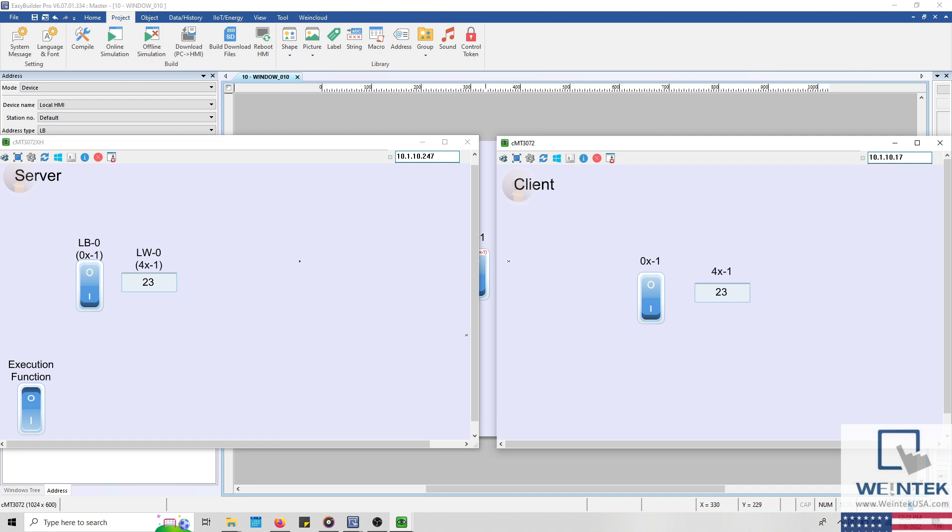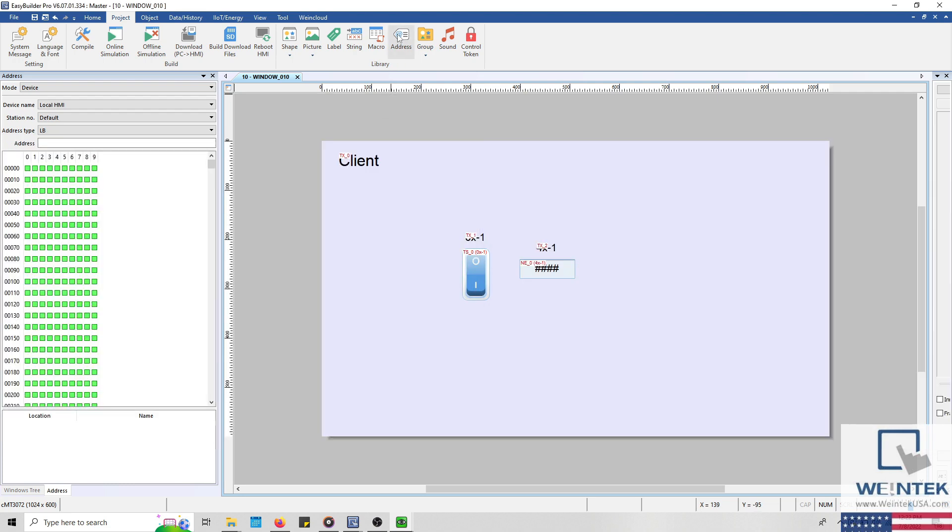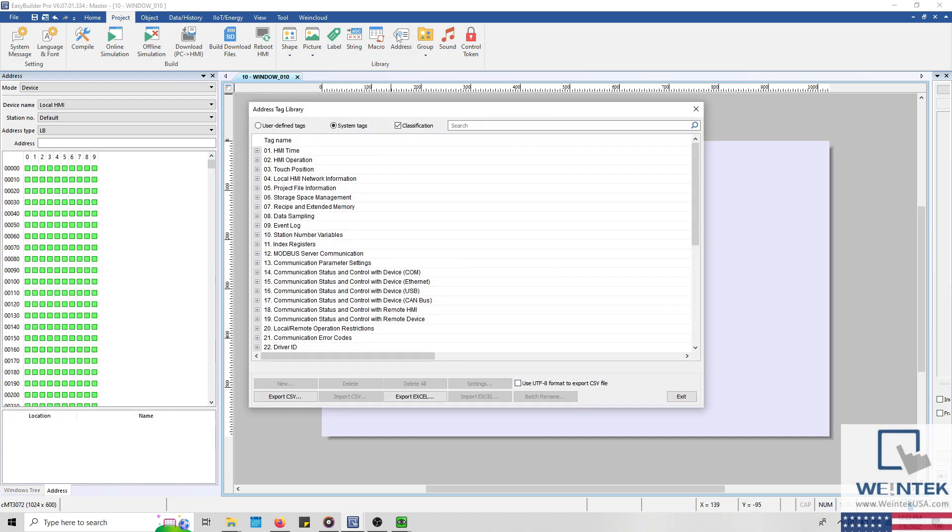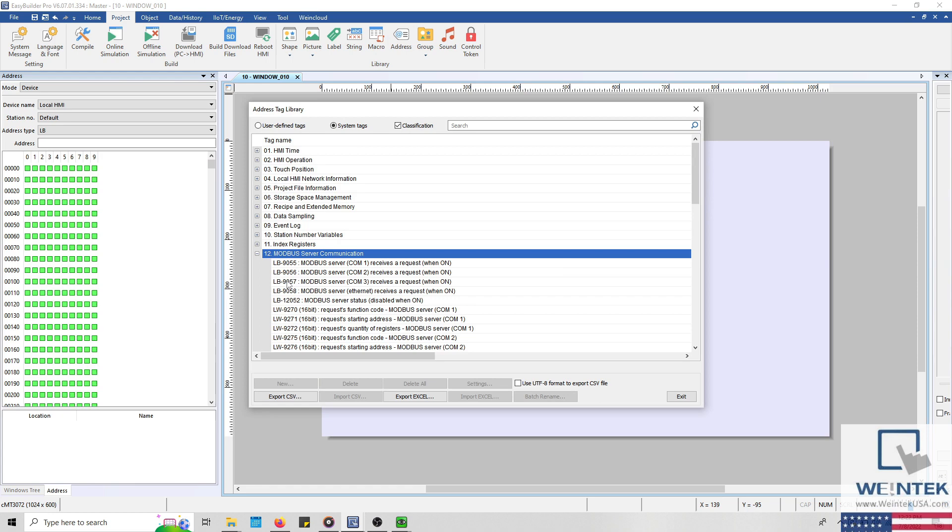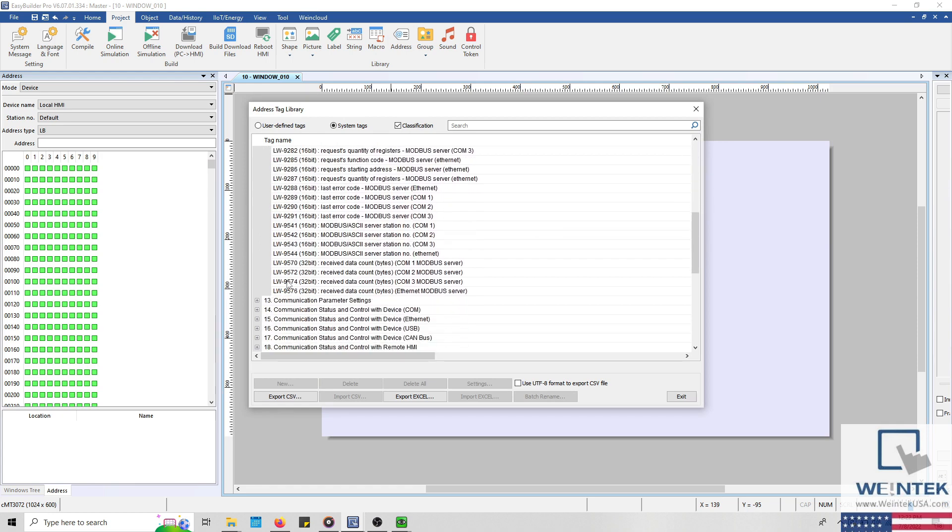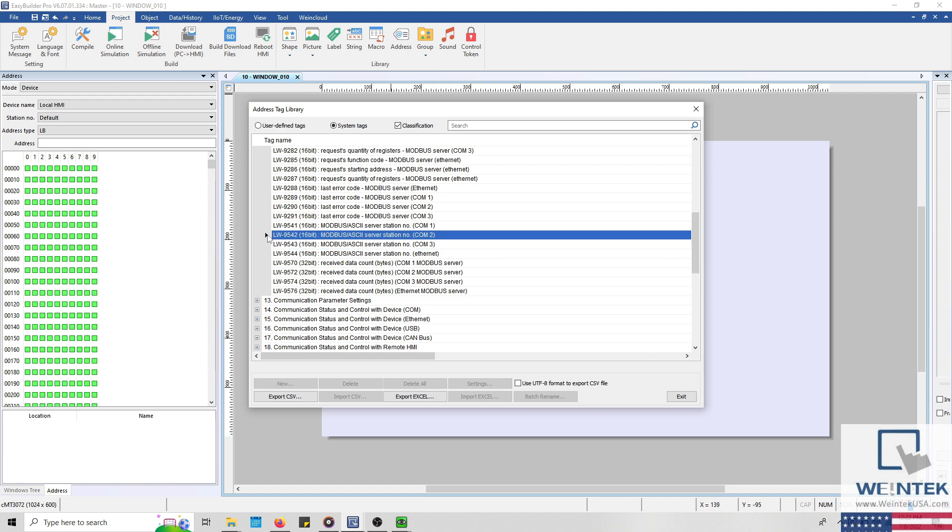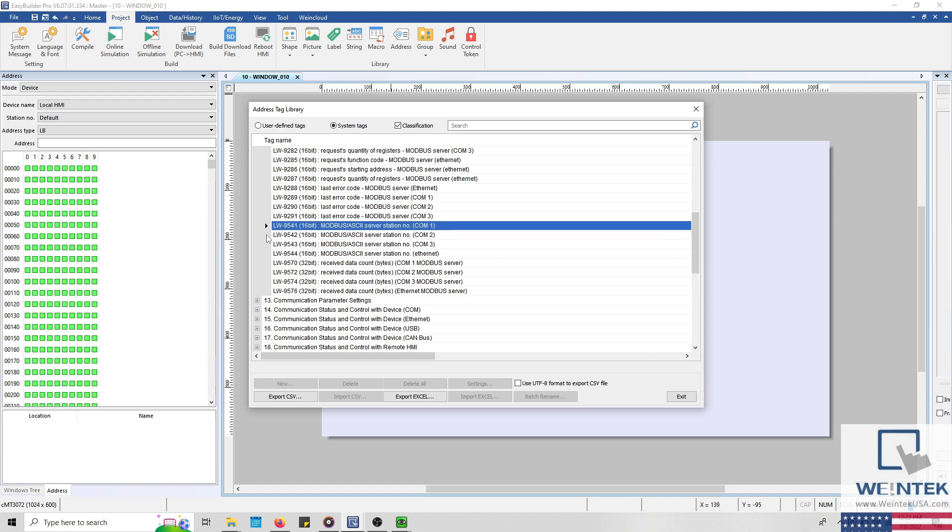Now, I would like to note that, if necessary, it is also possible to create a configuration screen for the Modbus server using system tags available within EasyBuilder Pro. Our software provides system tags that will allow you to update a Modbus server's station number during runtime. To add this to your project, create an object addressed to LW9544 or the system tag that corresponds to your selected interface. During runtime, the station number can then be configured by the operator or an engineer.